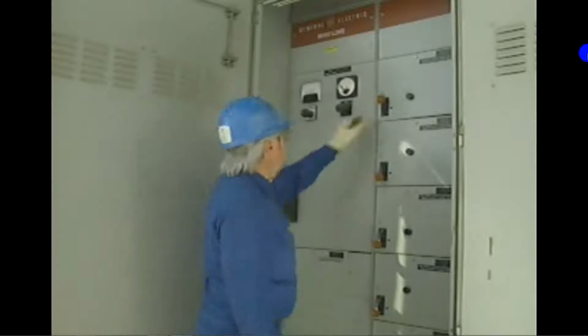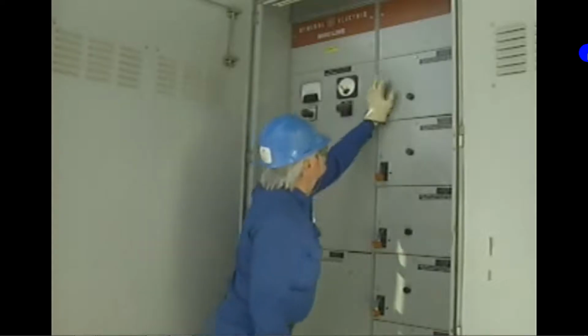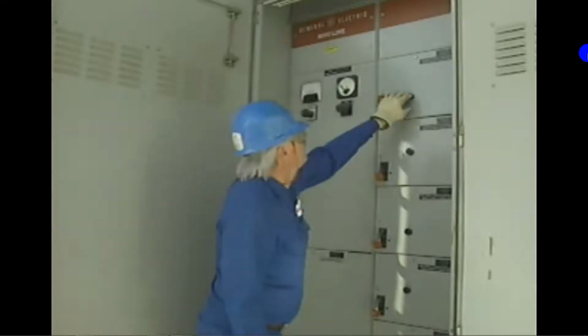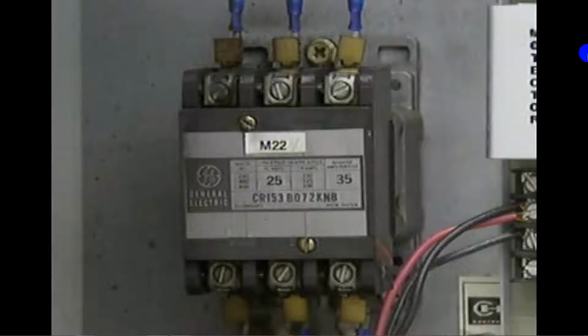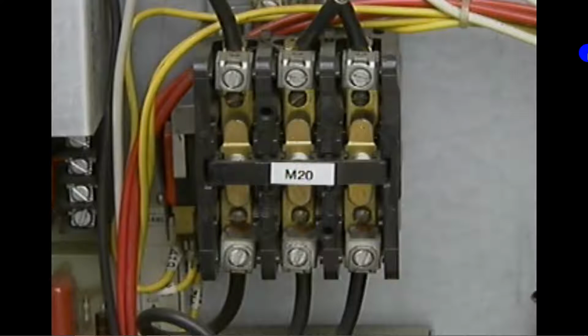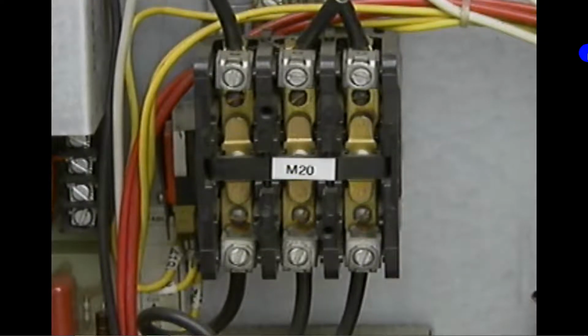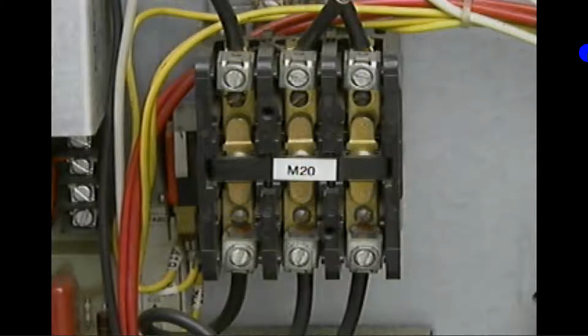Magnetic controllers move contacts by means of electromagnetic switches instead of push buttons or other switches. One type of electromagnetic switch used in magnetic controllers is a contactor. Generally speaking, a contactor is an electromagnetic switch in a controller that directly controls the power to a motor. When the contactor is energized, an electromagnetic field moves an armature that closes sets of contacts to complete a current path from a power source to a motor.